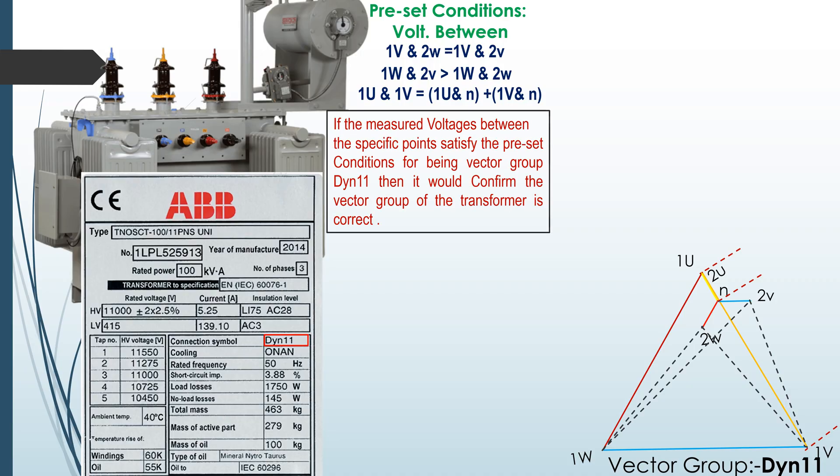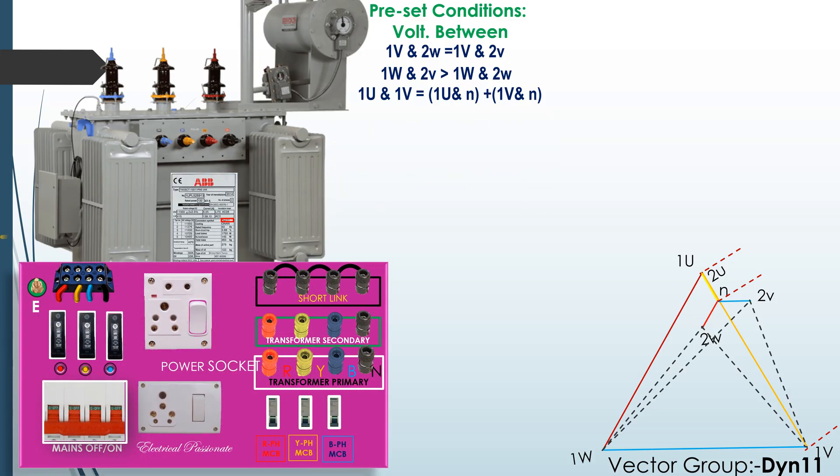If the measured voltage between specific points satisfy the preset conditions for being vector group DYN11, then it would confirm that the vector group of transformer is correct.